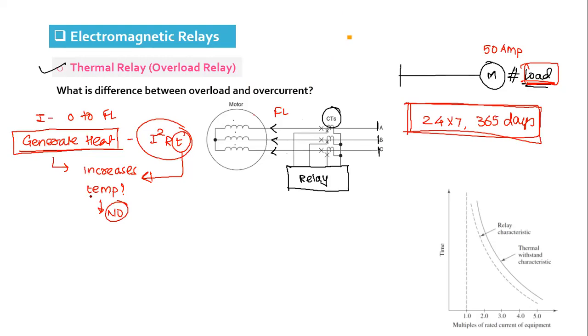Why will temperature not increase? Does anybody remember? Yes, correct, your answer is correct. Because there is heat generation as well as heat dissipation in any equipment. Just like the motor running in some environment, there is a difference between the winding temperature and ambient temperature. Suppose the winding temperature is, for example, 50 degree centigrade and ambient temperature is 30 degree centigrade.